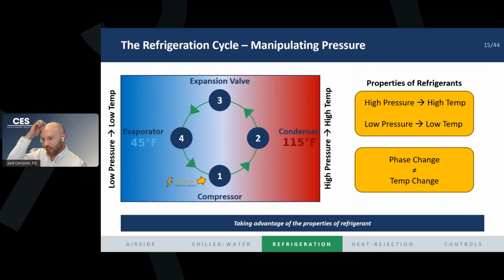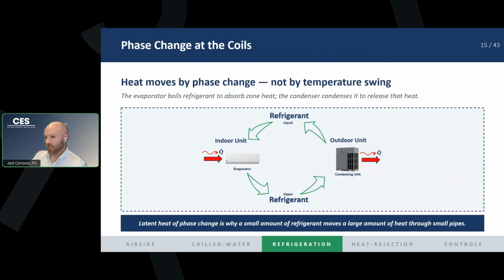Another way to put it is that the left side in this situation is going to be our low pressure, low temperature side, and our condenser is going to be our high pressure, high temperature side. We're manipulating the pressure to achieve the temperatures that we need. And as I just said, we're moving heat by phase change. In our evaporator and our condenser, we're not changing temperature, we're changing the phase. A very important property of refrigerant, and any fluid, is that by changing the state, we actually pack a bigger punch in BTU transfer. So we're moving a lot more BTUs by changing the phase than we are just by changing the temperature. Really, the most powerful way we can move heat is by evaporating or condensing our refrigerant, not by just changing the temperature of it.